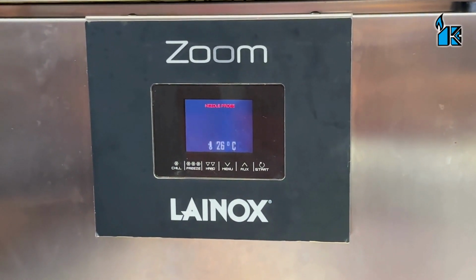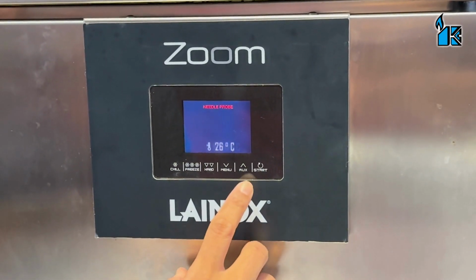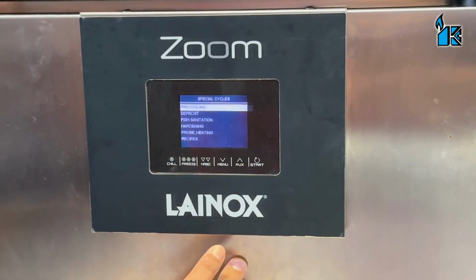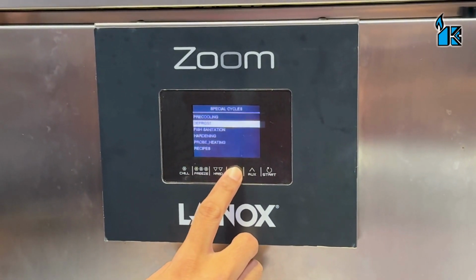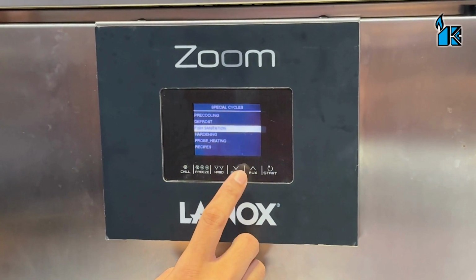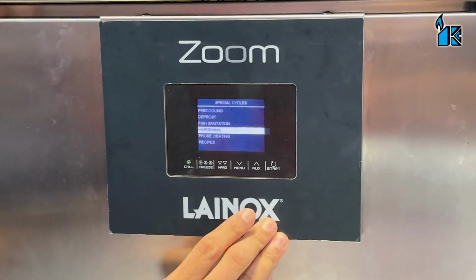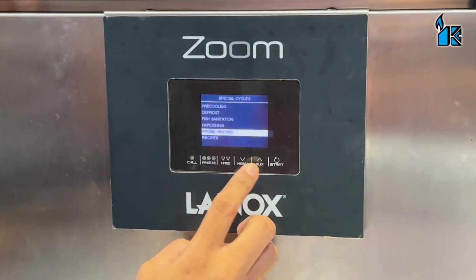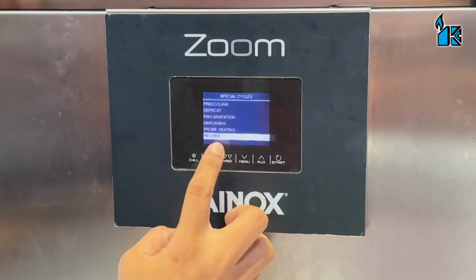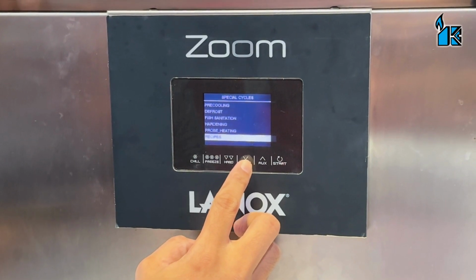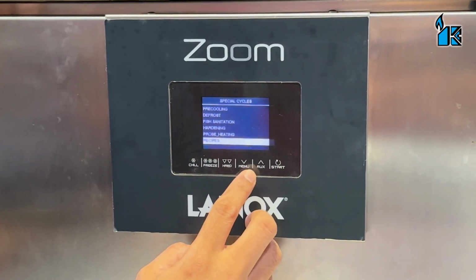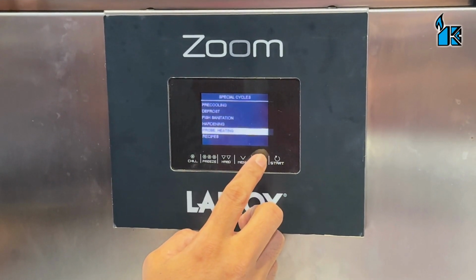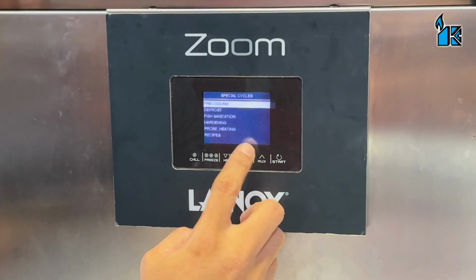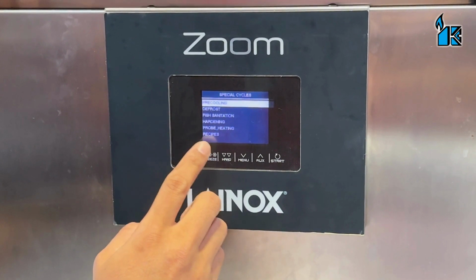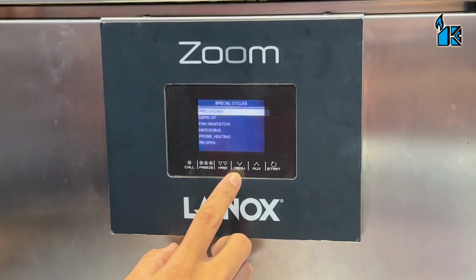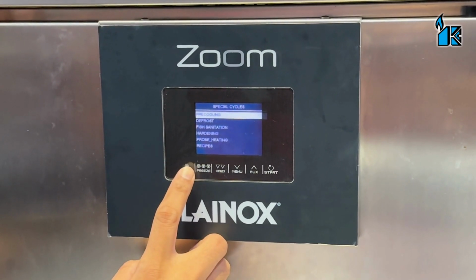For this machine, they have a few extra features. You can see when you press the AUX button, they have pre-cooling, defrosting, fish sanitation, hardening for ice cream, probe heating, and recipes. Recipes is where you can create your own program and save it inside the machine. So you can select any of these programs, depending on your usage. If you want to go back, just press chill.